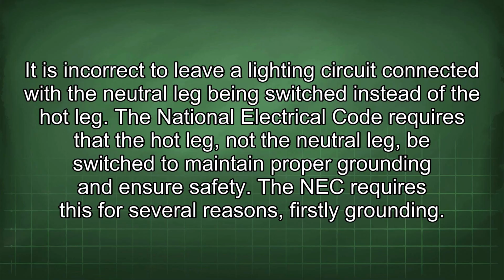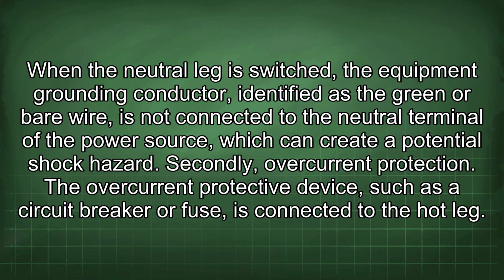It is incorrect to leave a lighting circuit connected with the neutral leg being switched instead of the hot leg. The National Electrical Code requires that the hot leg, not the neutral leg, be switched to maintain proper grounding and ensure safety. The NEC requires this for several reasons. Firstly, grounding. When the neutral leg is switched, the equipment grounding conductor, identified as the green or bare wire, is not connected to the neutral terminal of the power source, which can create a potential shock hazard.